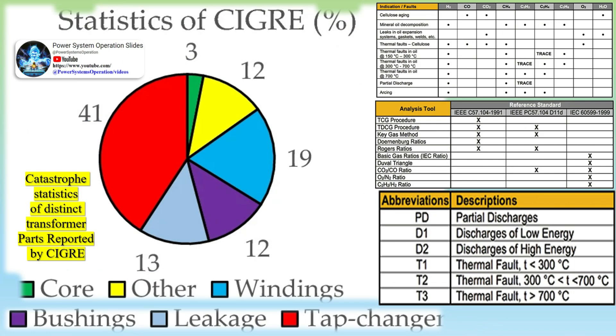DGA is performed on an annual basis to determine the levels of gas dissolved in the oil. However, one in three transformer failures occur within 12 months of testing, sometimes due to gases going undetected between testing cycles. Therefore, online DGA monitoring provides a continuous look at the gases in the main tank.